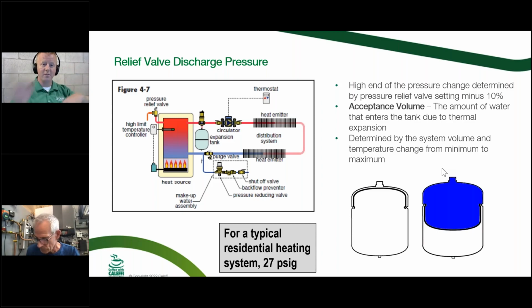It'll also make sure that when the system all turns on, those air vents, which are really good at letting air out, aren't letting air back in, because they're also really good at that too. So you want to make sure you're keeping the air out of the system, pushing it out with that 5 psi. Now, as far as your maximum operating pressure, it really has a lot to do with what your pressure relief valve is set to. If you want to keep it pretty tight, make sure the expansion tank is sized properly, but there might be some scenarios where you can get away with a slightly smaller expansion tank and you're just going to have a little bit more pressure increase in your system. And as long as it's okay, then knock yourself out, kind of thing. I don't know if you have any thoughts on that, Bob.